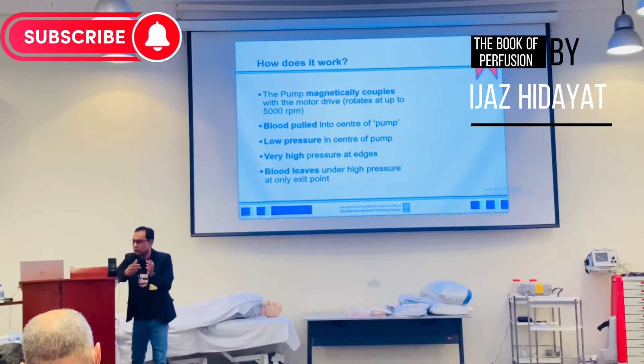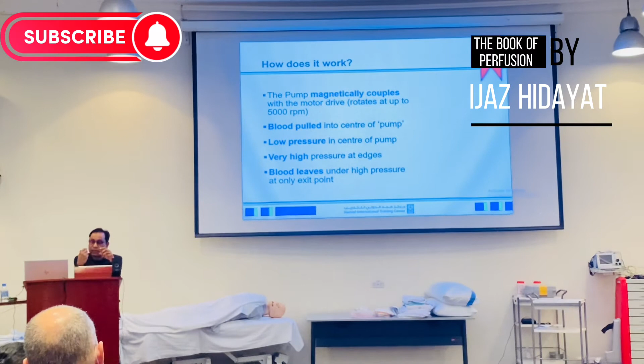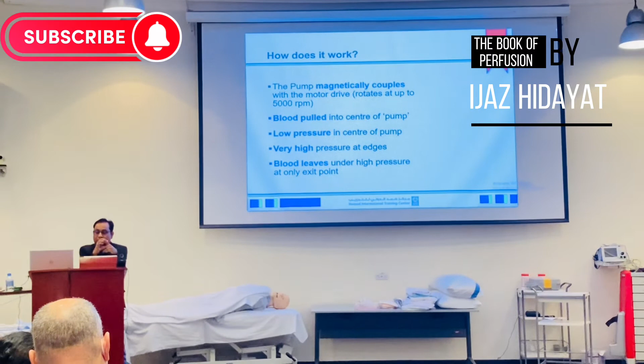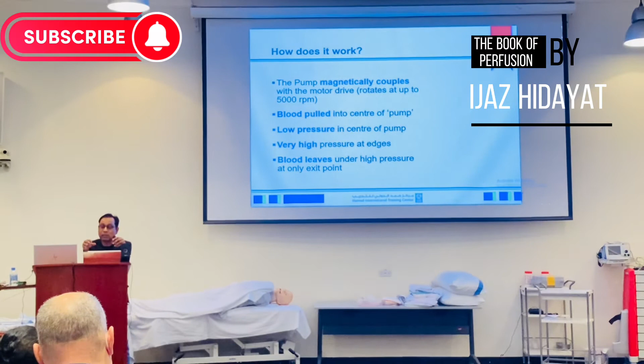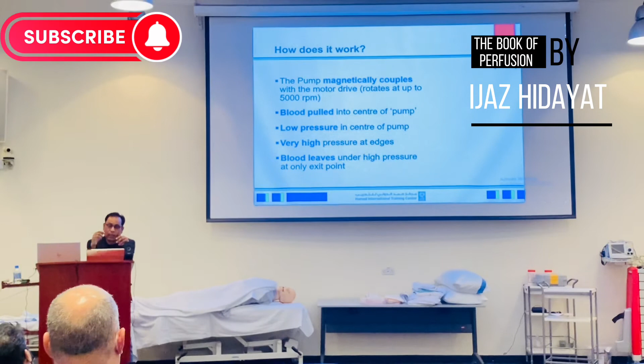When the pump motor and the magnet couple together, it starts centrifuging, and you will get some revolutions per minute with the help of the motor and the magnet. And they create a negative pressure in the center and positive pressure in the outer layer of the body. So this is the reason our center part is sucking blood from the access chamber, and the outer part is returning it back to the patient.